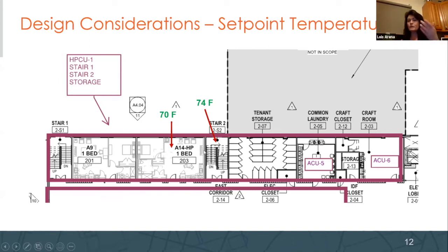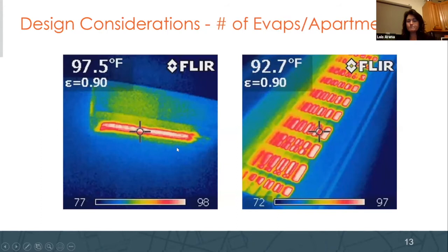So they're driving the refrigerant flow in the lines. And as long as you have refrigerant flow, you have this heat bleed that's going into all of the spaces on the same zone, because it's like a refrigerant loop. You can't have anybody just completely cut off. The condenser wouldn't run properly. So even if this stairwell was set at 70, like the apartment, it would run more often. And if this apartment didn't need heat, it would still get heat. And so you're going to wind up with overheating.